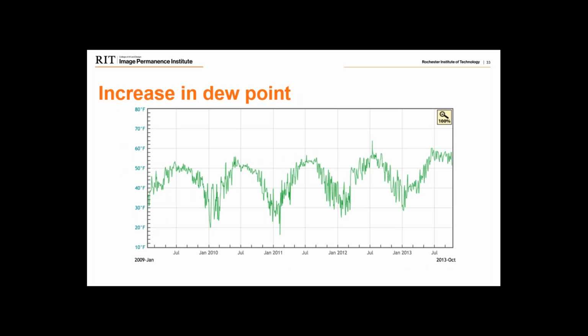Okay, so this increase in dew point comes from a space that had a cooling coil that was initially designed to provide a 45-degree dew point. And if you remember from previous discussions, dew point is what is going to determine the combination of temperature and relative humidity that you can get within a space. So the lower the dew point, the better combinations of temperature and relative humidity for preservation that we can achieve. And the higher it gets, the fewer options we have for creating a good preservation environment.